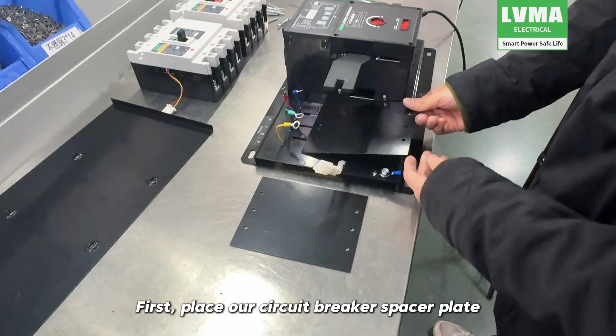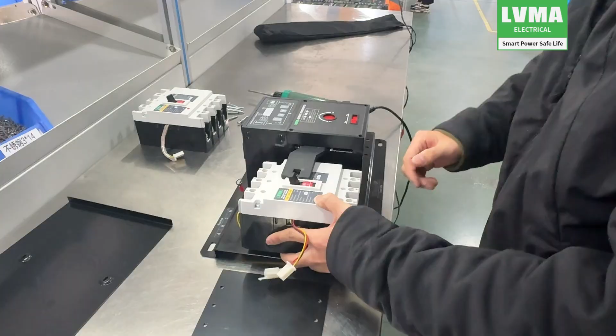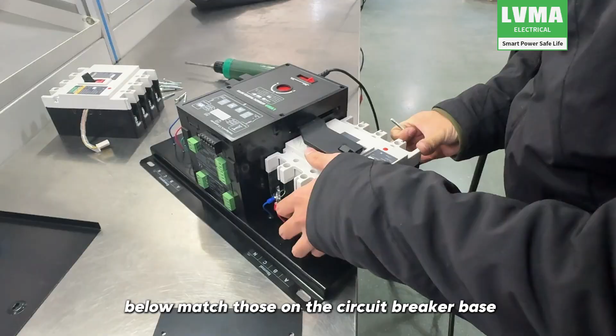First, place our circuit breaker spacer plate onto the ATS mounting base plate. Then, position the MCCB on top. Next, align and securely plug in the auxiliary alarm wiring harness. Ensure the clips are fully engaged, and that the holes on the spacer plate below match those on the circuit breaker base. Then, insert the corresponding fixing screws into the MCCB.